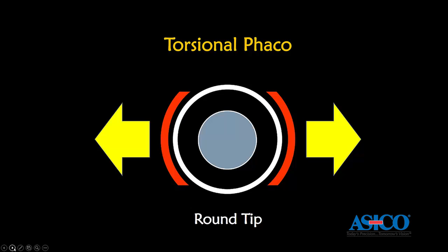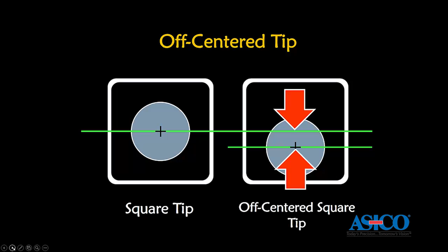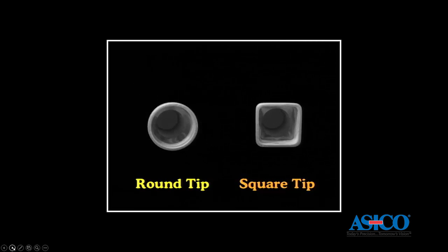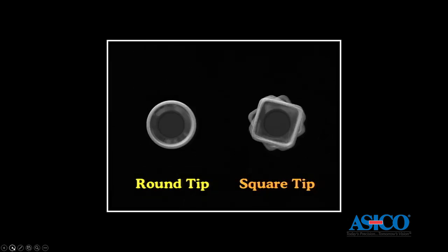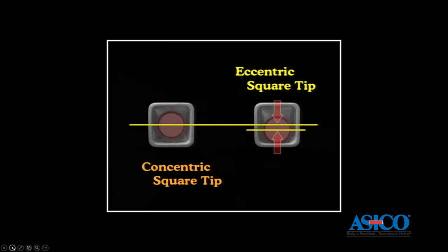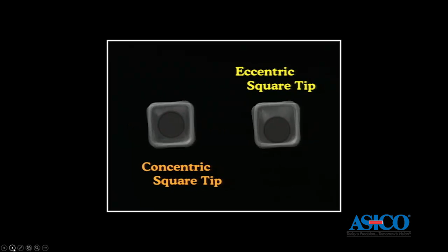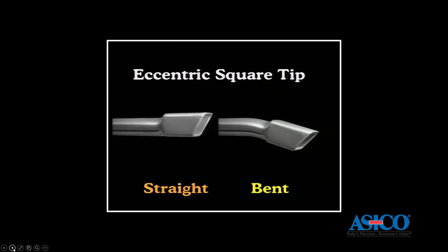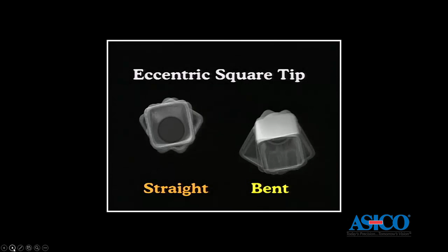Because in the torsional handpiece, the lateral part of the tip plays an important role to emulsify the nucleus. So I modified this tip from round to square so that the cutting efficiency can be maximized. And also I placed the aspiration port of the shaft off-center to the shaft. So with this off-centeration, the tip can create a wobbling motion. Nothing happens in the round tip if you use it on the torsional handpiece, but if the tip is squared, it can make a cutting efficiency, and if the tip is off-centered, it can create a wobbling motion of the tip. So by off-centering the tip, the cutting efficiency of the square tip is enhanced. And also, if the tip is bent, the wobbling movement is enhanced more. So this is the idea of the Harmonyx tip.